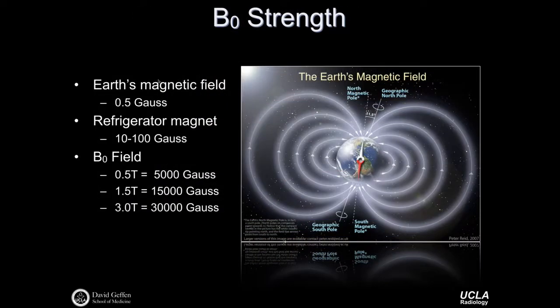Regarding B0 field strength, the Earth's magnetic field is about half a Gauss, and a common refrigerator magnet is about 10 to 100 Gauss. The B0 fields used in MR imaging are on the order of 5,000 to 30,000 Gauss—considerably stronger than the conventional magnets we encounter in everyday life. This gives rise to important safety considerations because these very strong magnetic fields can pull ferromagnetic devices or objects into their field very quickly and with great force.